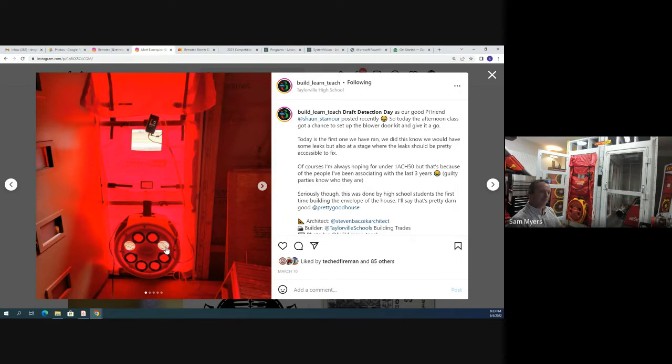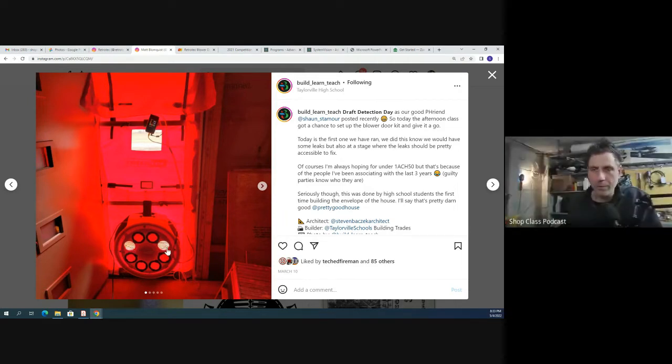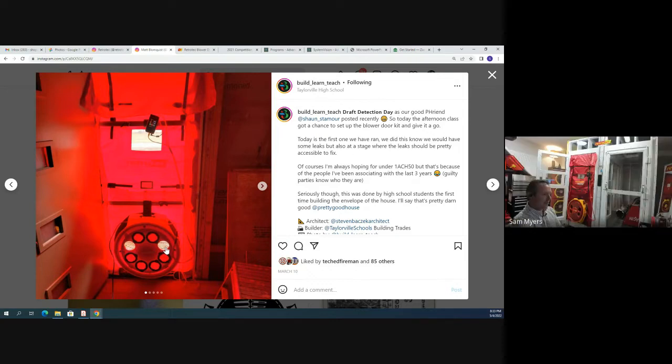It gets under pressure immediately. And is that these two holes that are open right here? Yeah, you have these different hole configurations here. If you can see mine, I've got 4 open because that's what it takes for me to get this room under pressure the way I have it set up. But you can think about it as gears in a car. You have to keep a certain amount of pressure inside of that fan shell for the manometer to take a reading. If it's too open and the blades aren't spinning very fast, you're not going to really read a flow. It's just not going to pick up. So you want to choke it down so you're building up more pressure in there so those blades start spinning to get that pressure on that second channel.